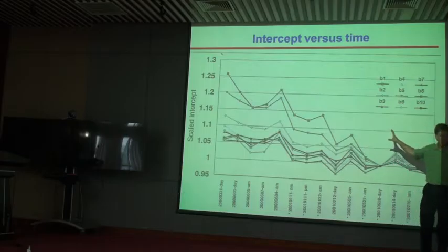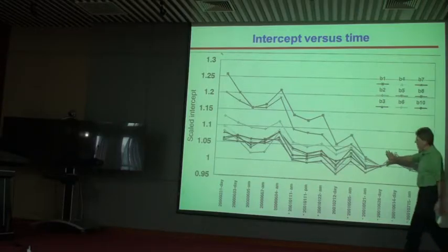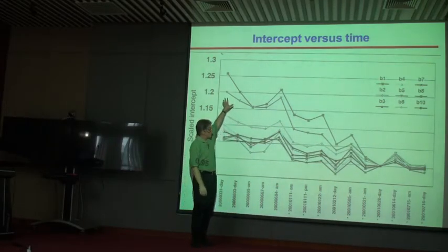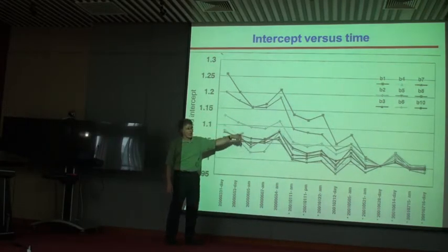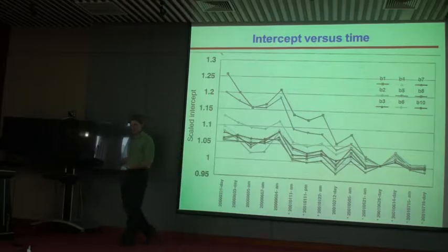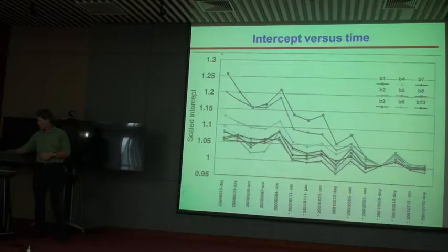And this is one of the older ones, so we knew we had this, which is why you would basically go ahead and do calibrations about every 3 to 6 months, because you wanted to take into account this change in time in some of the bands. If you do not account for that change of 25%, and you try and treat the aerosols, you're going to get a different aerosol type. You're going to get a different Junge parameter. So this is one of the uncertainty sources that we have to be concerned about.